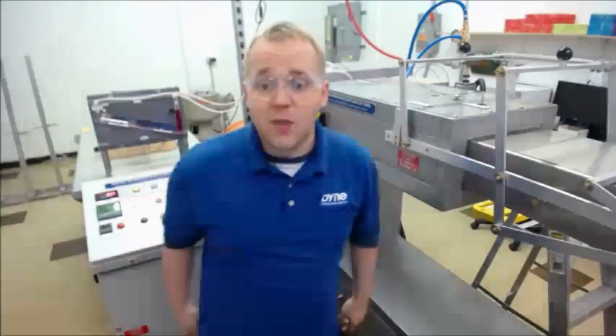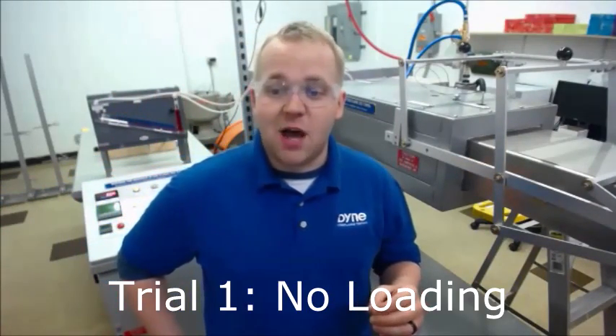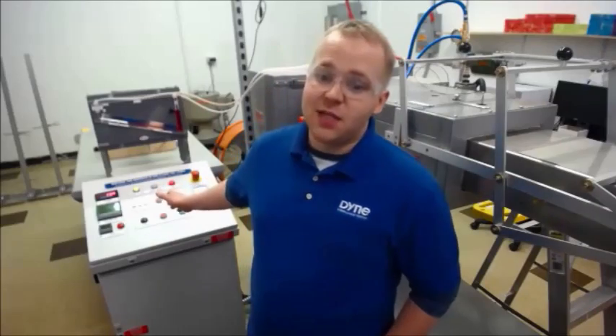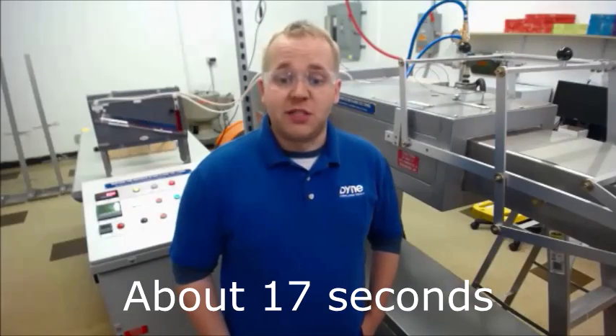My test plates have already been prepped, so let's get started. My first round will be with no loading. I'm hoping you'll be able to hear the sound of these glass bulbs breaking, and I'll also call out the times as we go. The machines are a little bit loud so you might not be able to hear it. The timer will also sound as soon as the bulb breaks — it's set up to a sensor that detects pressure loss in the line used to pressurize the head. Note that these heads should be going off in about 17 seconds.